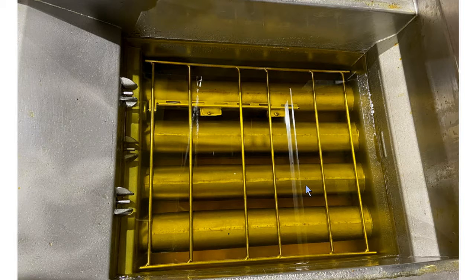The logic behind an E22 error code is that it's looking for a rate of rise of temperature from your temperature probe. Right here's your temperature probe. You have a level probe here and here. And then you can see the oil within the fry vat. And these are your heat exchange tubes that pull the flame through to heat the oil. What can happen is if the customer doesn't have it full of oil, so I have oil covering my heat exchange tubes, but my temperature probe is not in the oil, it's looking for a rate of rise in temperature on a cold start for 120 degrees and below.